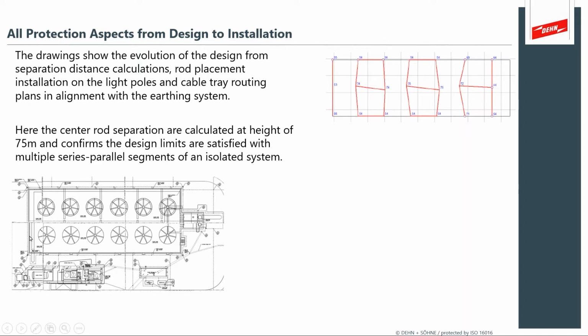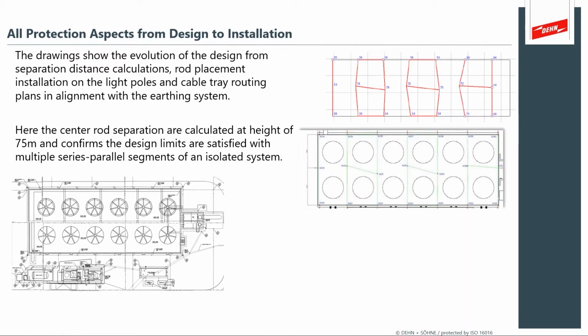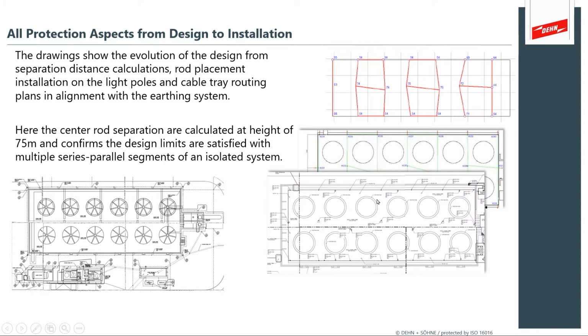So we take a look at a structure like this, and we estimate the spacing of the lightning air terminals, and from that we can calculate the separation distance. So in an illustration like this, we see the initial calculation of separation distance. Then we can apply the actual intended design. And so here the next illustration that you see is the evolution of the design. Now we're applying the actual air terminals onto the system, and we're overlaying those air terminals onto the light poles that our customer might allow us to use. And so this gives us a really good target for where we're going to actually apply our air terminals.